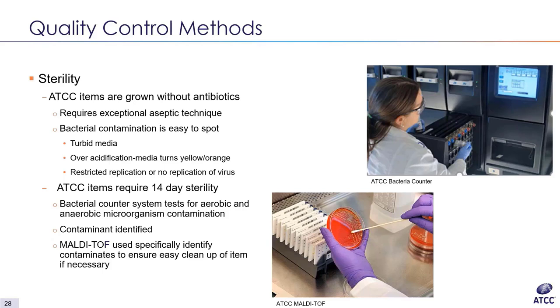At ATCC, sterility processes have evolved to use state-of-the-art technology for real-time detection of contamination events, allowing us to both detect contamination faster and specifically identify the contaminant quickly. Our bacterial counter uses individual bottles for testing for the presence of anaerobic and aerobic microorganisms, inoculated with a syringe to greatly reduce the possibility of cross-contamination. MALDI-TOF (Matrix-Assisted Laser Desorption Ionization Time-of-Flight) is used to determine the pattern of proteins in an intact bacterial or fungal sample and can identify bacteria, mycoplasma, and fungi using only one colony.